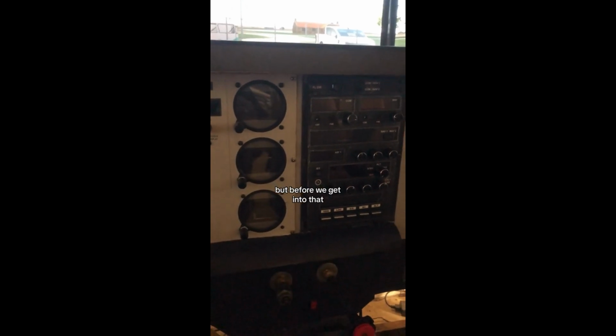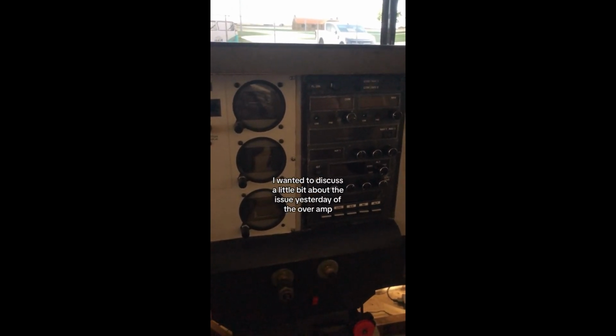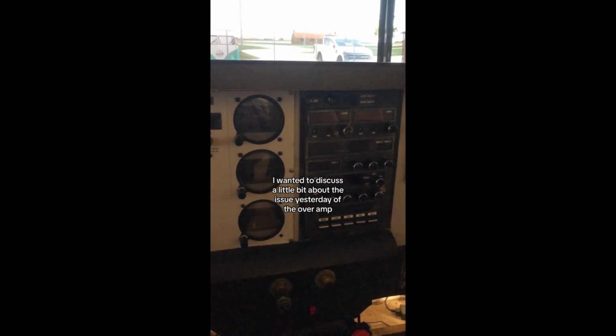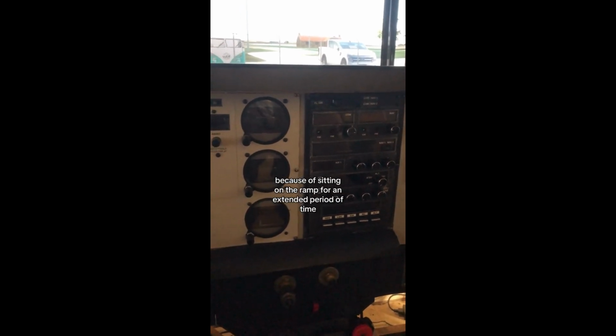But before we get into that, I wanted to discuss a little bit about the issue yesterday of the overamp, because of sitting on the ramp for an extended period of time with all of the electrical instruments, lights and whatnot on. So what happened was during that time it's just draining the battery.